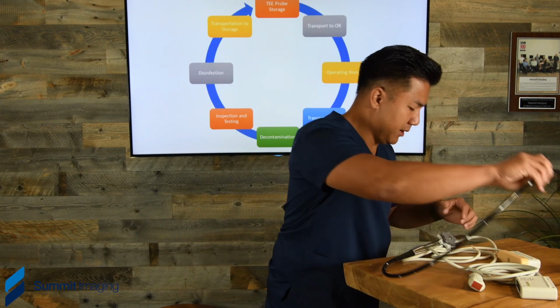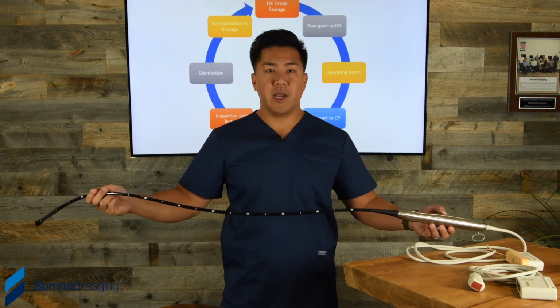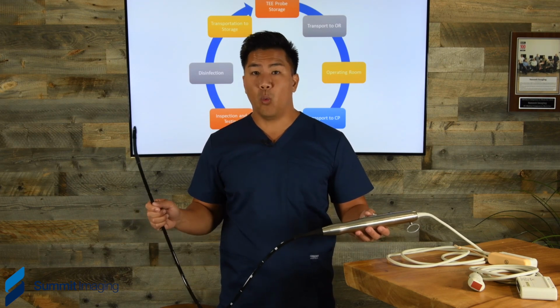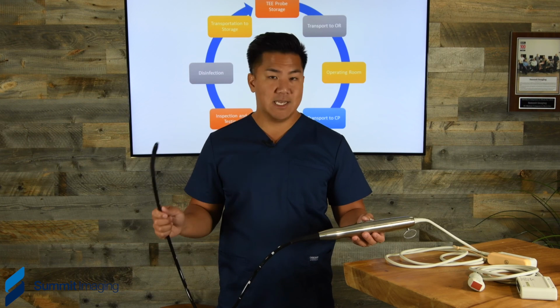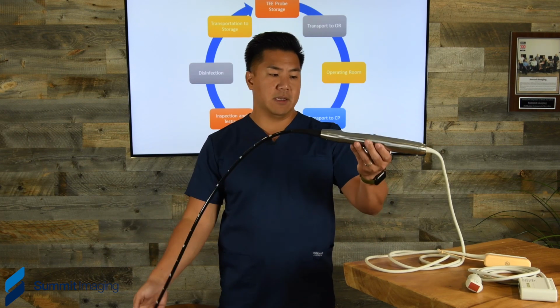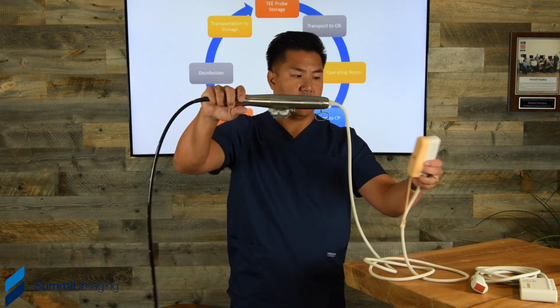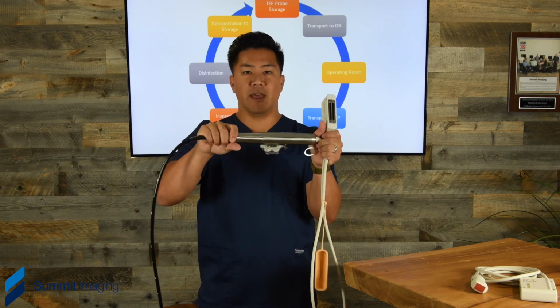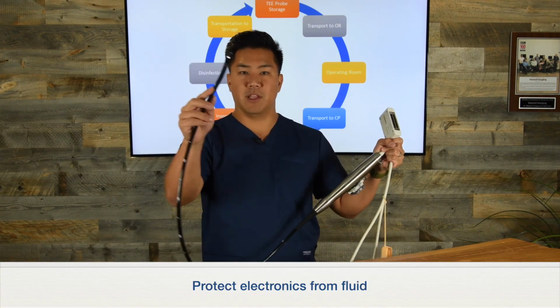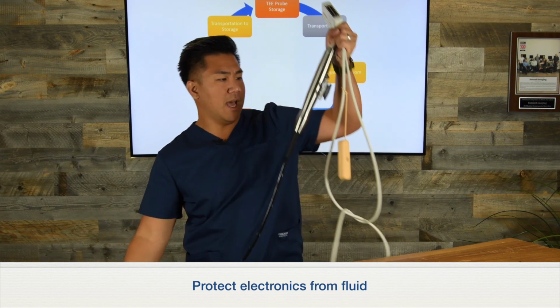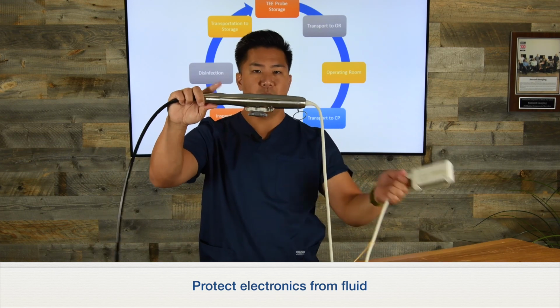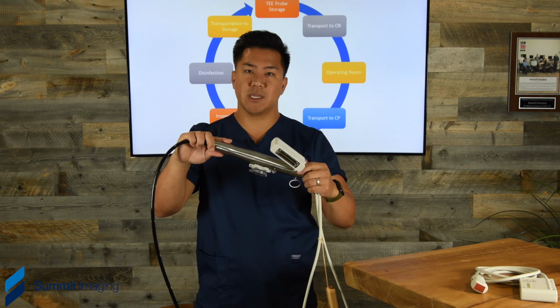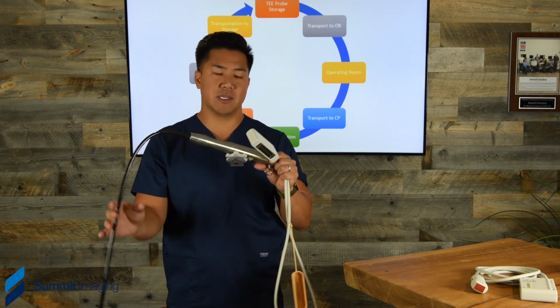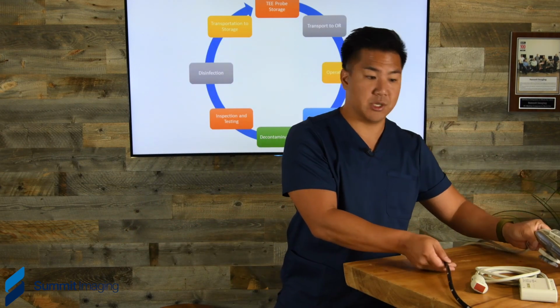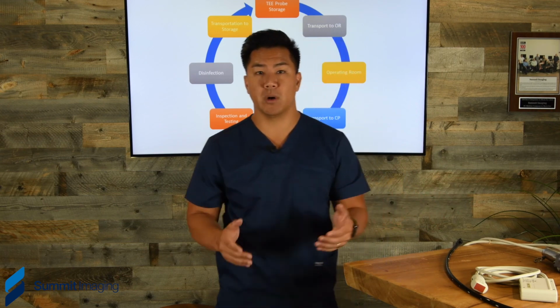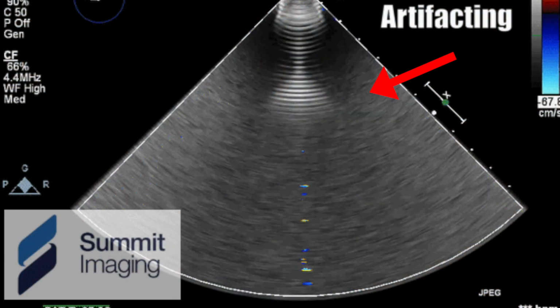And so specifically for TEE probes, there's two areas that we've seen where you do not want any fluids, water of any type to enter. The handle and the connector have very sensitive electronics that don't have the types of protections that the electronics in the tip of the TEE probe do. And so what happens is these may be washed during the decontamination process. Now we have fluid ingress into electronics that, the first time you power that up on the next study, can cause some extreme shorts and actually cause massive failures in the equipment itself.